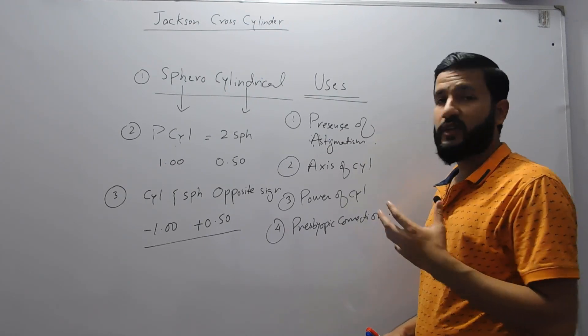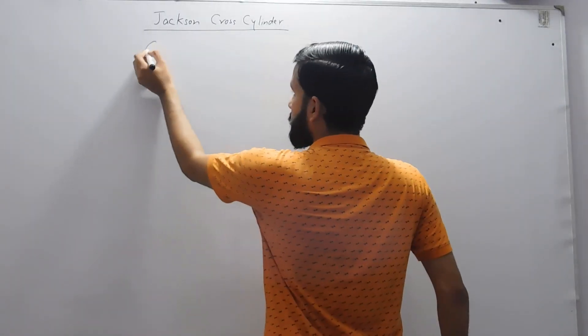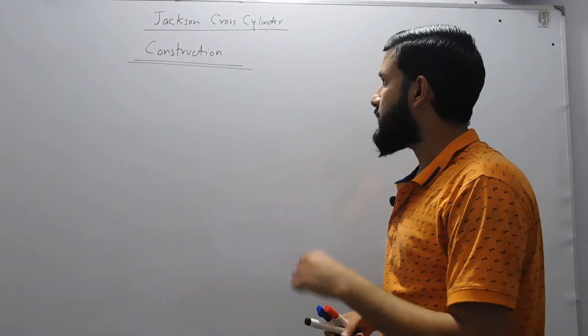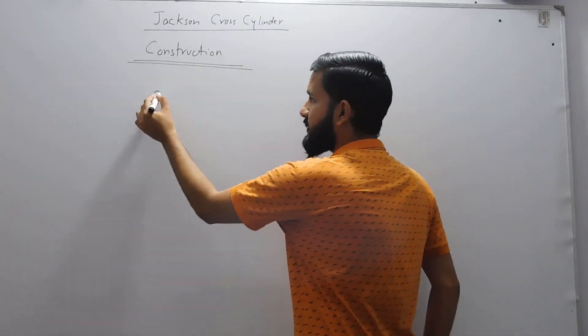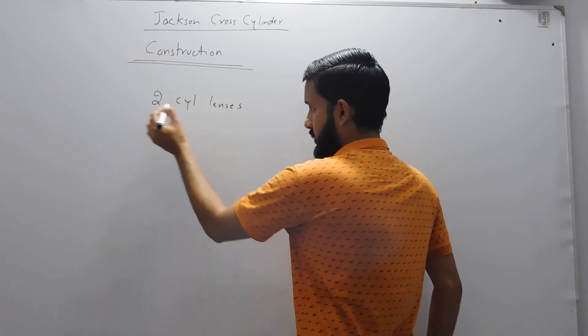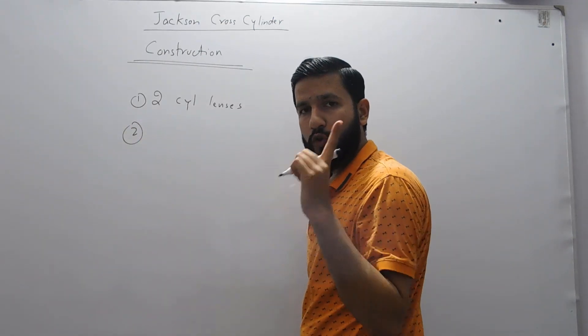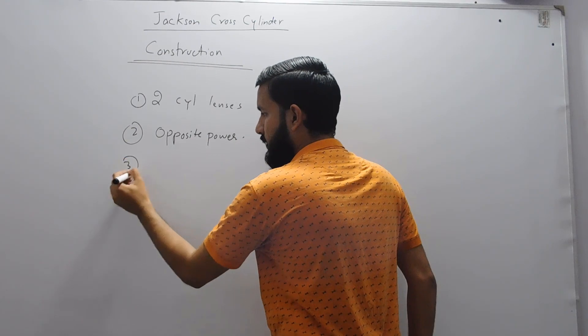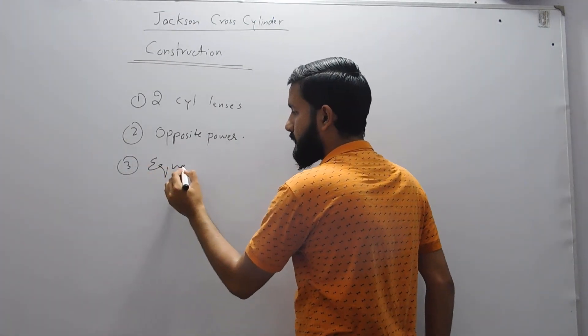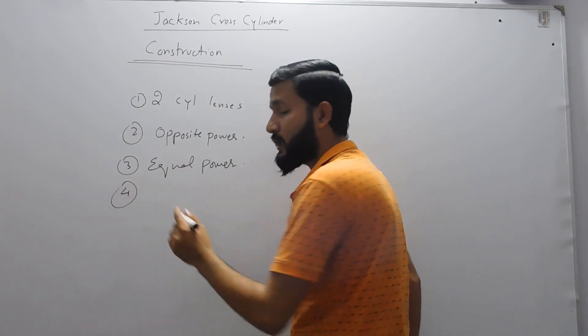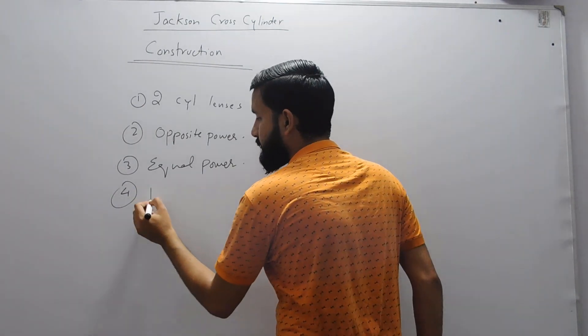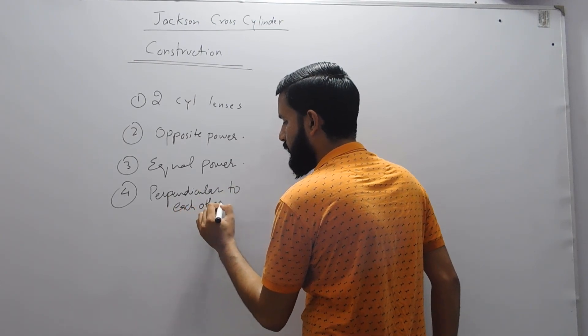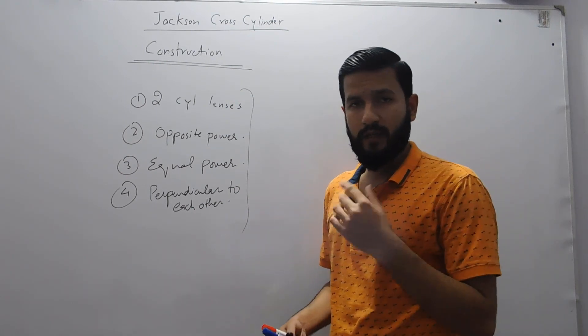Next we will move towards the construction of the cross cylinder — how it is made. To make a cross cylinder you simply need two cylindrical lenses. Number one, they should be of opposite power. Number two, they should have equal power. Number three, they should be held perpendicular to each other. If you follow these steps, you can easily make a Jackson Cross Cylinder.